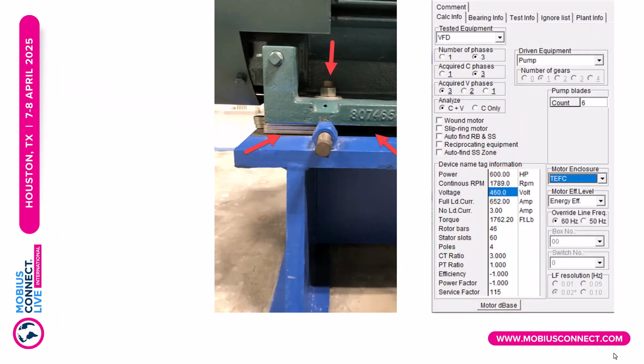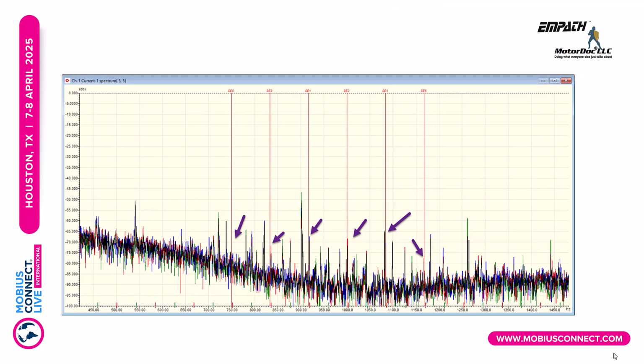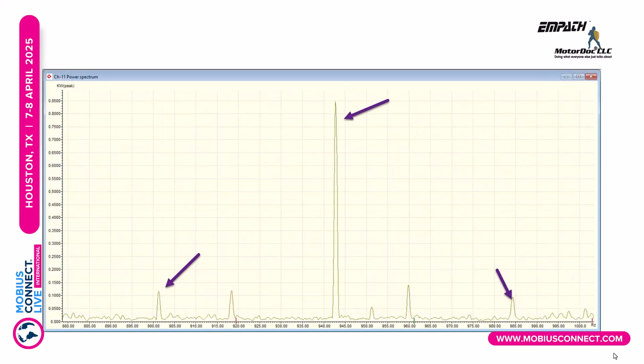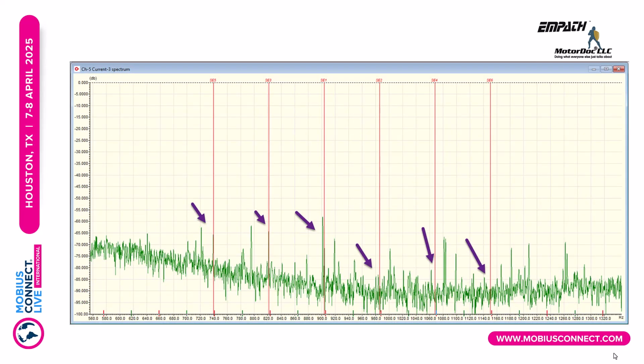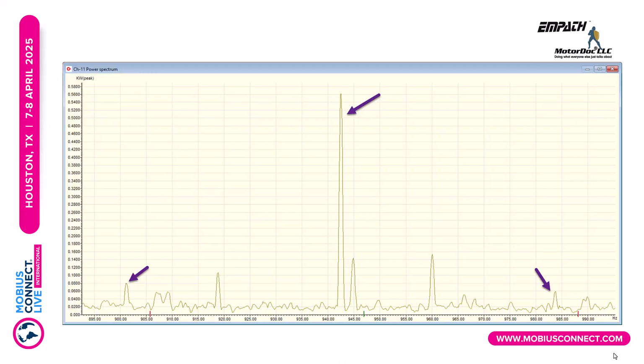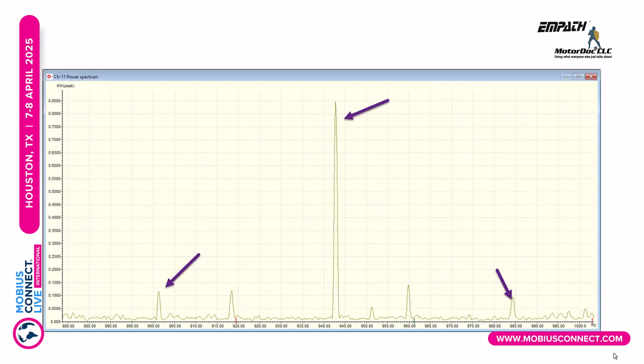So let's take a look at that foot issue. This is static eccentricity in this case. There's my peaks associated with static eccentricity, 0.85, 0.1, 0.1, so that's about 1 kilowatt. The other part had to do with another alignment, but they didn't fix the feet. In any case, 1 kilowatt, again, it goes back to that other condition we were looking at.